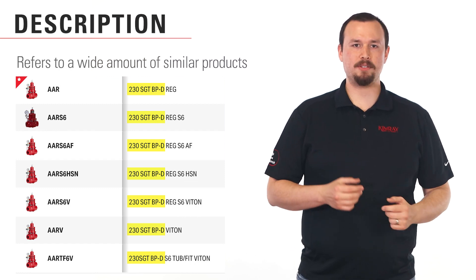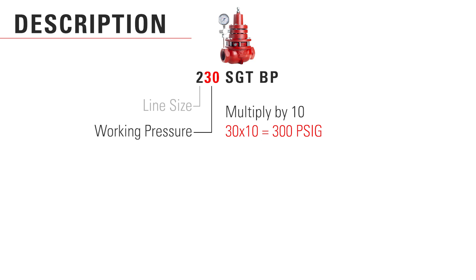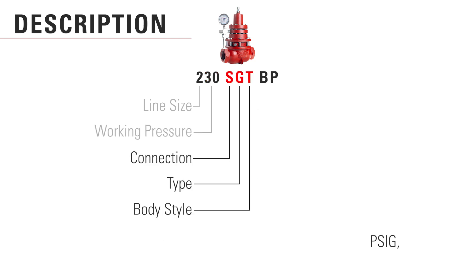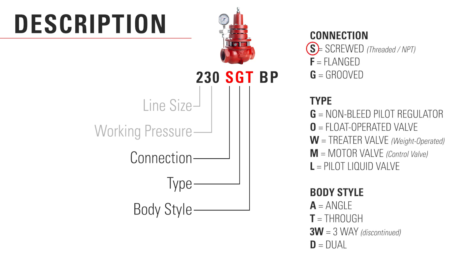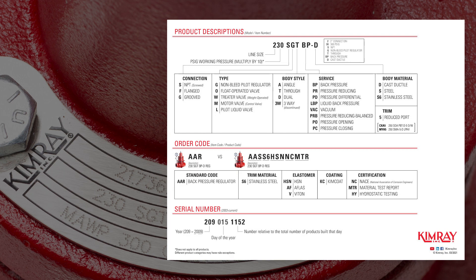Here's what the numbers and letters on this description mean. The first number is the line size — 2 inches. The second number can usually be multiplied by 10 to get the working pressure of the product. In our example of the 230, this would be 300 pounds per square inch. There are a few exceptions to this rule, like our weight-operated valves. The next three letters tell us the connection type and body style — in this case, screwed, non-bleed pilot regulator, and through body. The last letters tell us the service the product is used for, which in this case would be back pressure. You can download this reference chart to help identify different product descriptions.